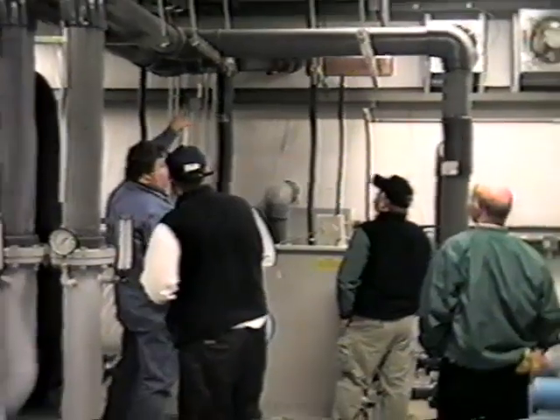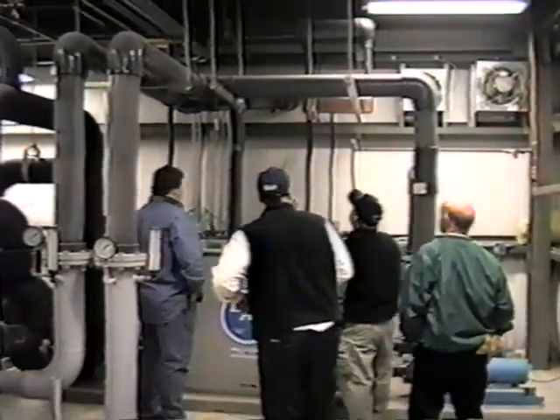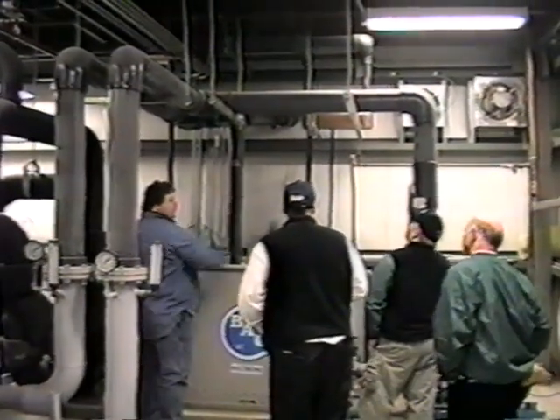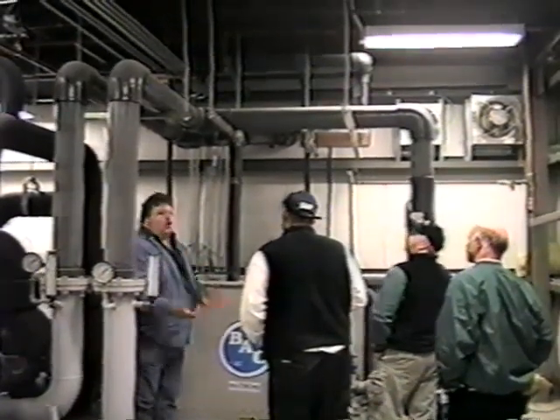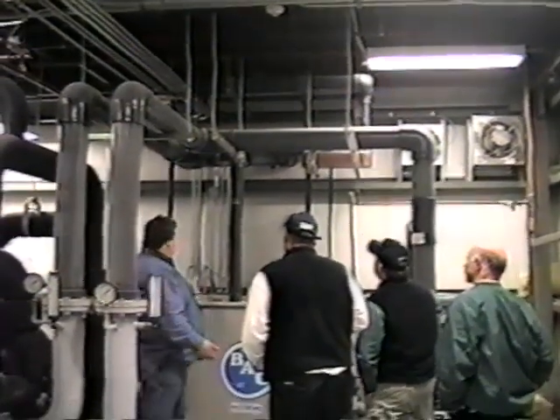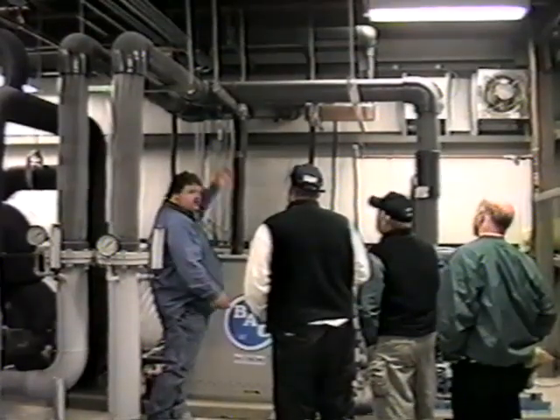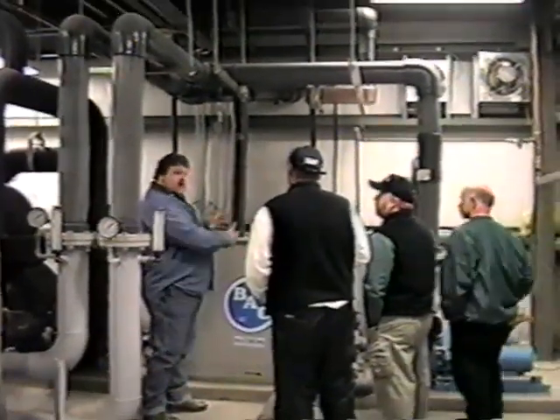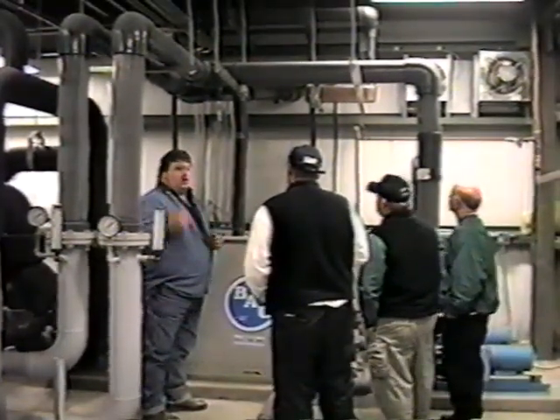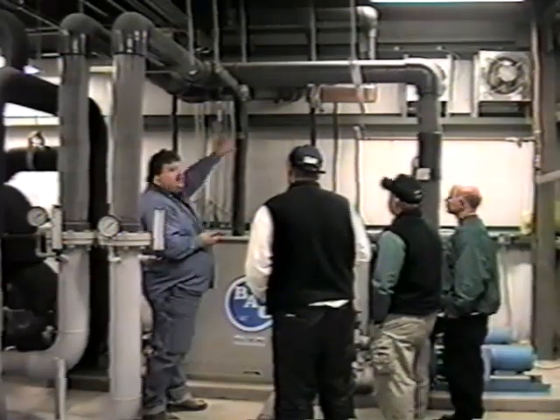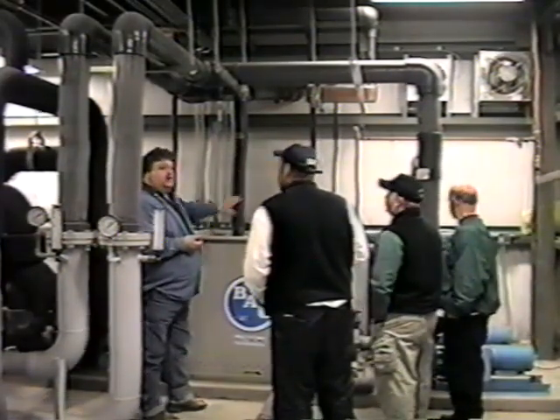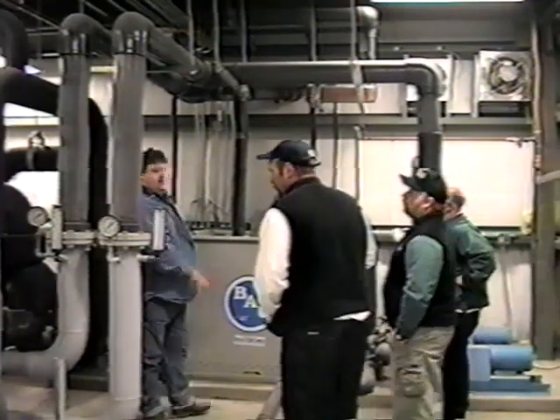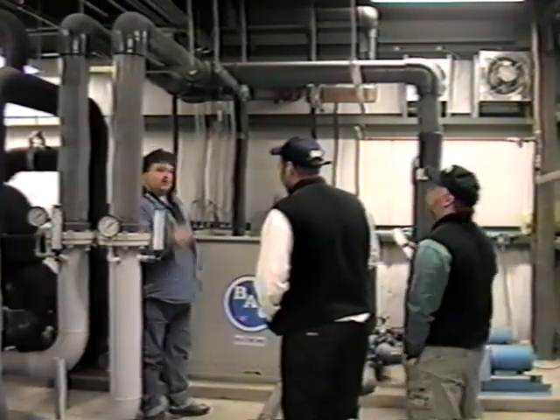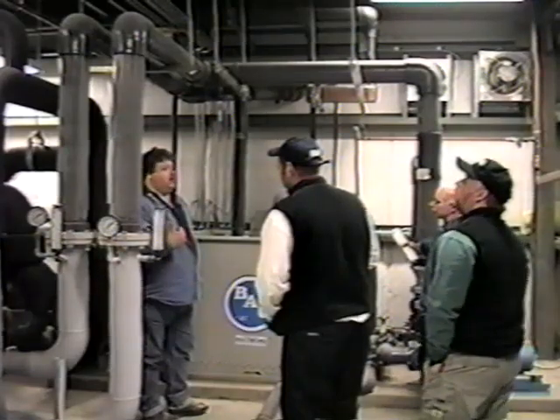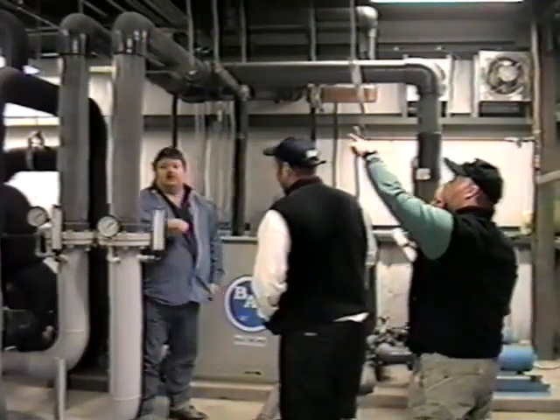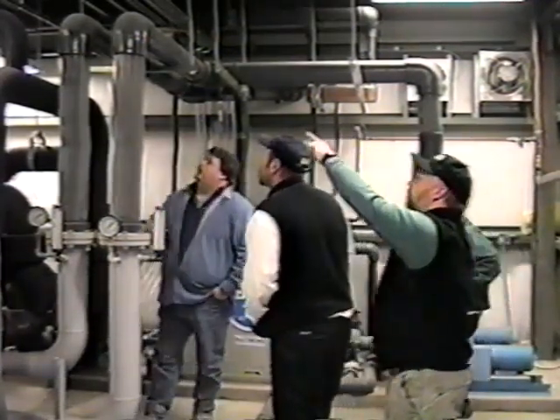I just have to put the operator on it, and that will do that function as the water warms up. If it's cold, the water just comes around this way through the system and stays inside the building. As the water gets warmer, we start passing it outside and getting rid of the heat. We want to keep the heat in for the chiller and for the underfloor heat. Anything we can grab that way is gravy. What is that thing that's on the?